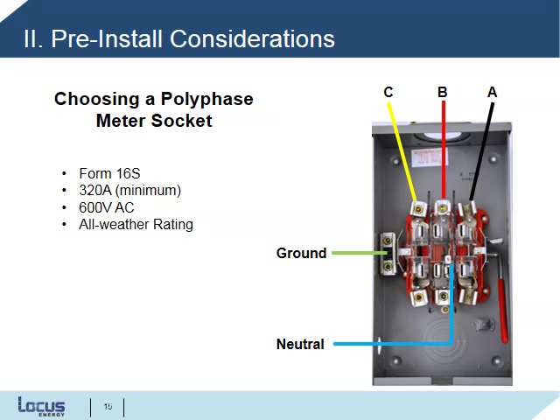For the LGate 320, it's important to select a meter socket with the following specs. It should be form 16S, rated 320 amps minimum and 600 volts AC. The LGate 320 requires neutral, whether you have a Y or Delta system. We recommend getting a meter socket with an all-weather rating for the LGate 320 as well. In this diagram, you can see the lugs for A, B, and C, along with ground and neutral in the center.